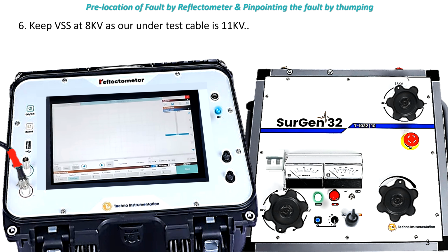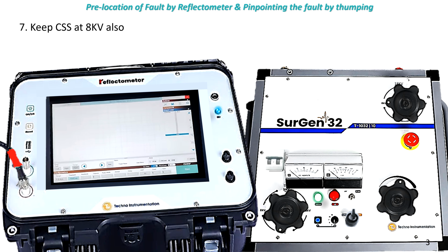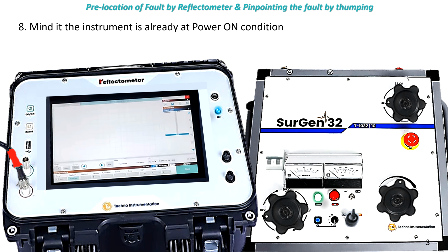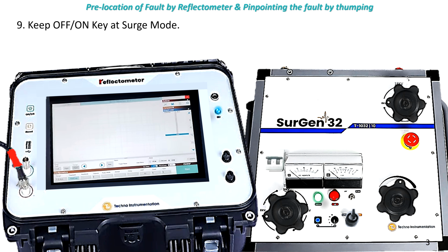Keep VSS at 8 kV as our under test cable is 11 kV. Keep CSS at 8 kV also. Mind it, the instrument is already at power on condition. Keep the off-on switch at surge mode.